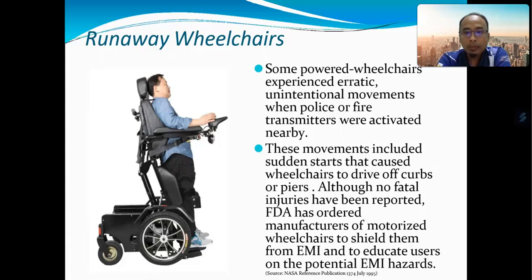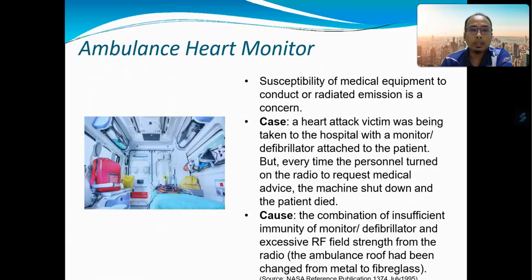Although no fatal injuries have been reported, the Food and Drug Administration has ordered manufacturers of motorized wheelchairs to shield them from EMI and to educate users on the potential EMI hazard. So this is also quite dangerous. We need to shield the system so that it will not be interfered with when police or fire transmitters are activated in those areas.